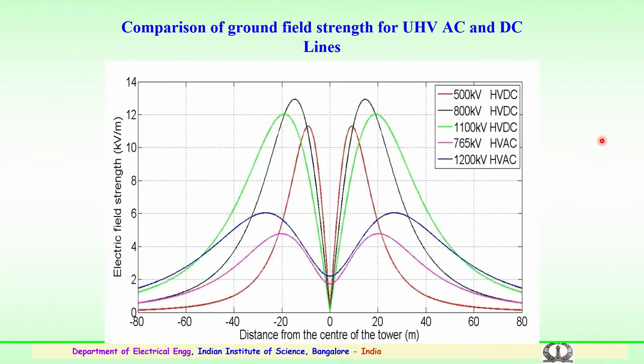Similarly, a comparison of the ground field strength for both ultra high voltage AC and DC transmission lines was estimated, and the comparison is made here. You can very clearly see the comparison for both ultra high voltage AC and DC lines for the electric field strength. This y axis shows the electric field strength versus the distance from the center of the tower. So for high voltage AC and DC, you can see the comparison. The red color gives the high voltage DC 500 kV line, which gives approximately 11 kV per meter, as we have seen in the previous case. Again, the 800 kV is 13 kV per meter.